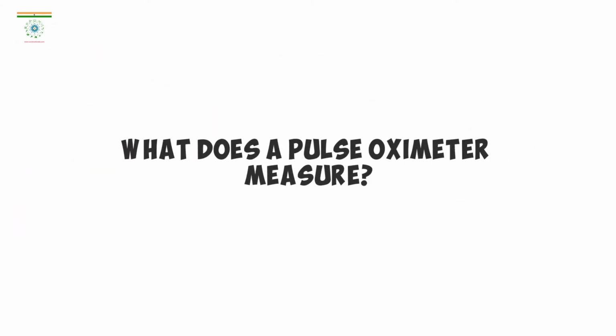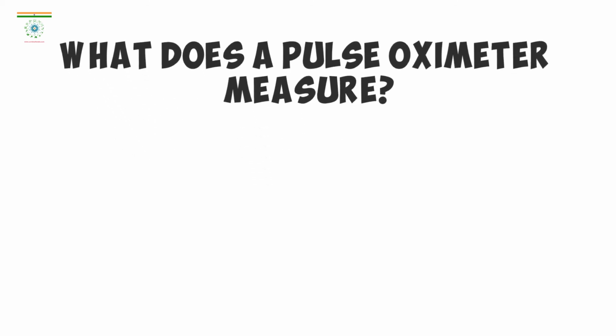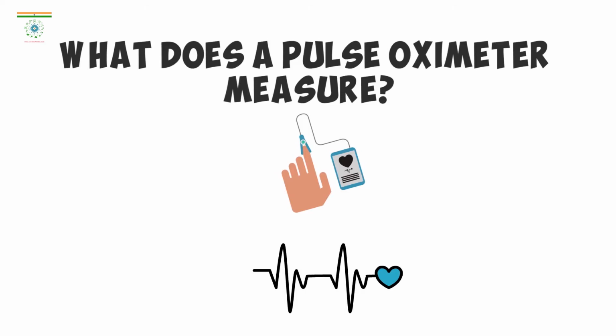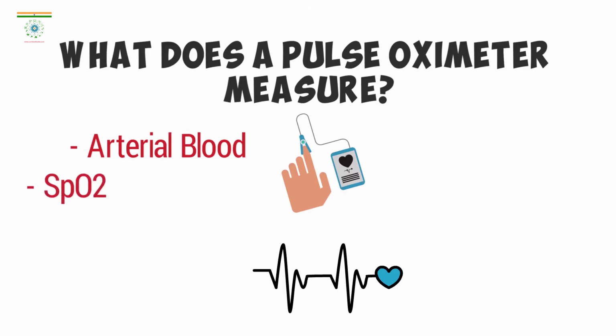So what does a pulse oximeter measure? Now, as we mentioned before, a pulse oximeter measures the oxygen saturation in the blood, and it gives a heart rate measurement. And when I say it measures the saturation of oxygen in the blood, I'm of course talking about arterial blood. More precisely, it measures the amount of oxygen that is being carried by hemoglobin, and this reading is known as the SpO2. So the primary function of a pulse oximeter is to measure oxygen saturation, and by doing so, the heart rate is automatically calculated alongside the percentage of oxygen.